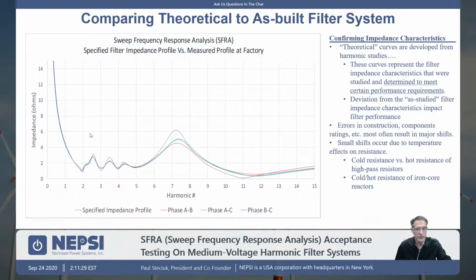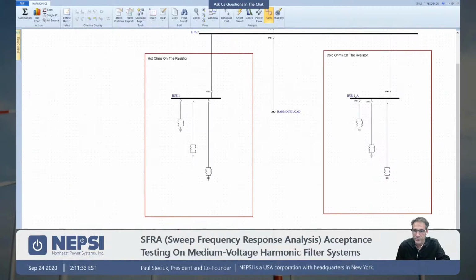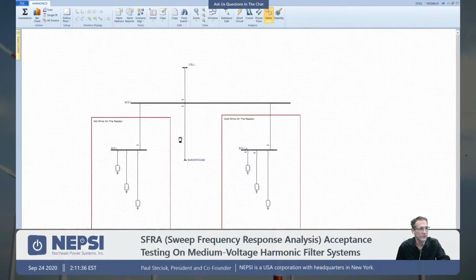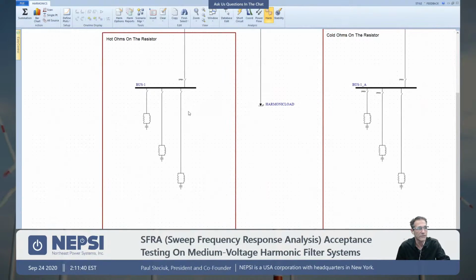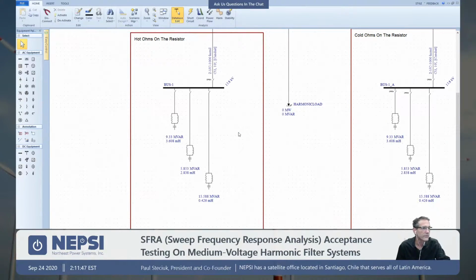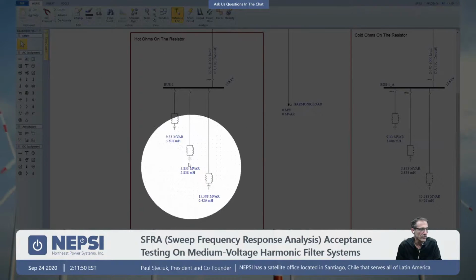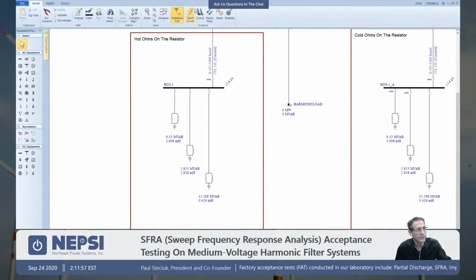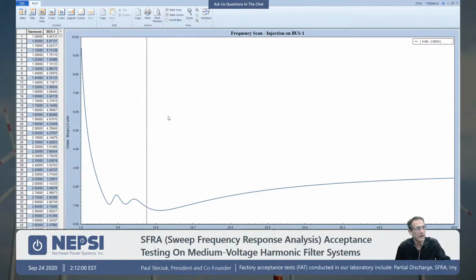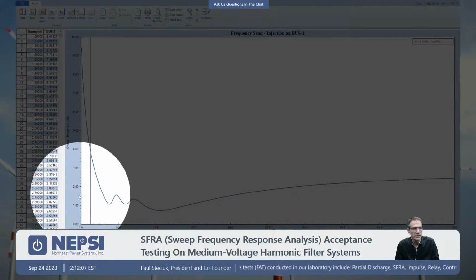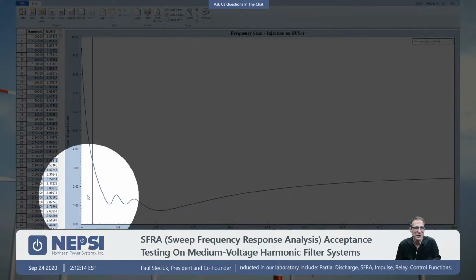So I'm going to flip over and just show you how this is typically done. If we do the harmonic study, we use a program called Easy Power. And I just took a very simple system here with the actual harmonic filter. Let me go to the database. You can see here we have 3 harmonic filter branches, and they're all high-pass filter branches. And I can put this into harmonics mode. I can double-click the bus bar, and I can actually get the impedance profile. On the x-axis we have harmonic number, and on the y-axis we have ohms.